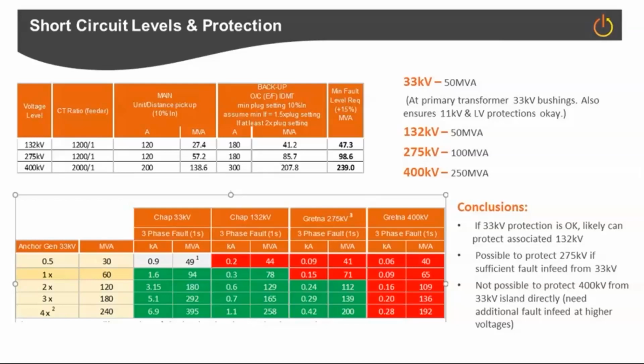But the work that we've done, based on our case study work, we've done some study work and actually proved that at least at 33 kV level, the current protections that are installed on the networks should operate correctly. You will need a minimum short circuit level of 50 MVA for them to operate, but assuming you've got a 60 MVA anchor generator within that power island, within that DRZ, then certainly at 33 kV and also at 132 kV, the next voltage level up, that should be sufficient and allow your existing protection systems to function correctly. The problem comes when you go higher up the voltage ladder.